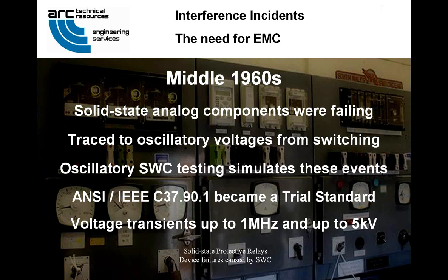In the mid-1960s, new solid-state analog components in protective relays were failing in substations. They were traced to oscillating voltages created from normal switching operations, not high current faults. The Oscillatory Surge Withstand Capability, or SWC, test simulated those events. It was first codified in the mid-70s as ANSI IEEE C37.90.1, then a trial use standard. The test simulates oscillatory voltage transients up to a megahertz at 5 kV or more on the control wiring that resulted from these switching operations. And of course, the equipment manufacturers at that time had to begin designing their equipment for immunity to these simulations if they wanted to continue to sell to the utilities.